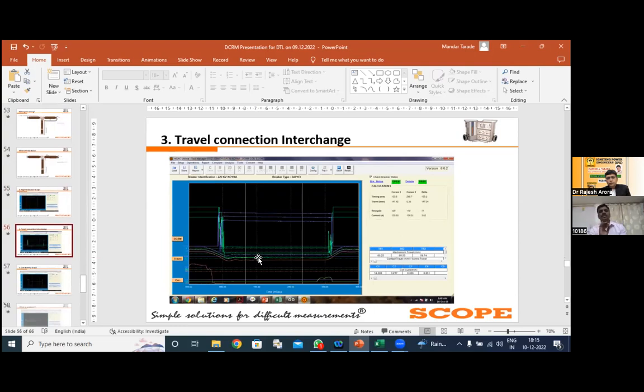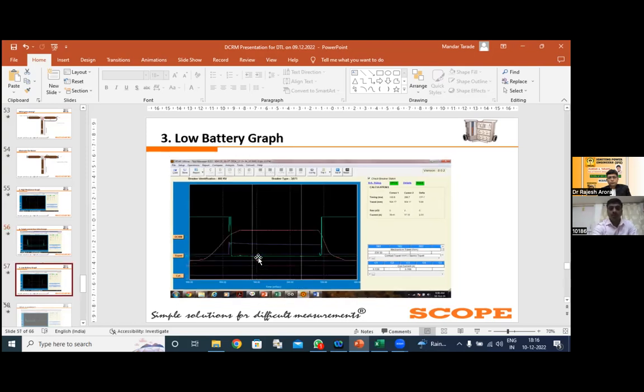Third thing is that if you are interchanging the connection of the travel, then you are getting the reverse graph. If your graph is reverse, then the values we get with the help of the travel traces, that is the total travel, contact travel or mechanism travel, will get hampered because of that. So the correct connection of the travel transducer plays a very important role.